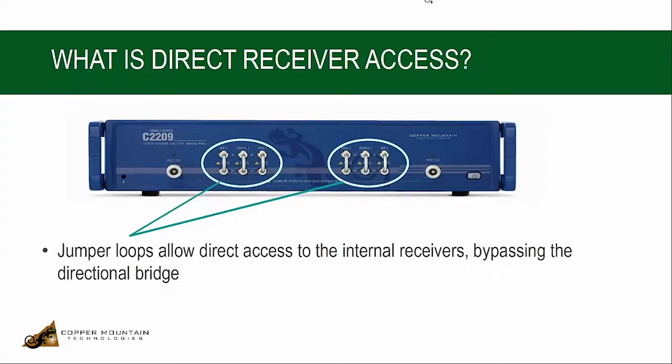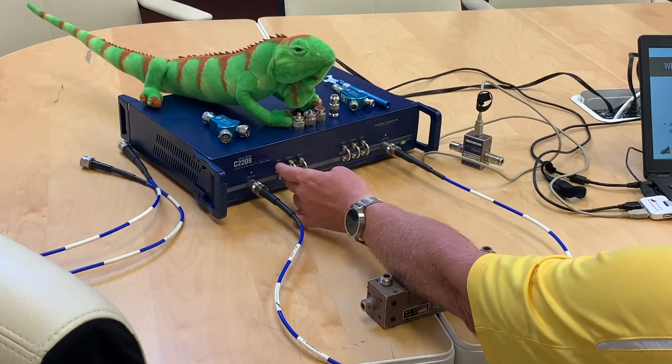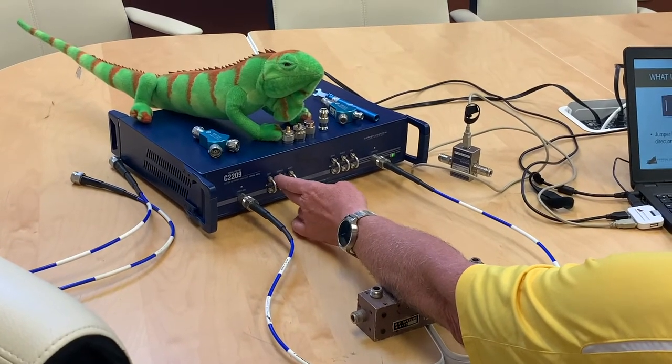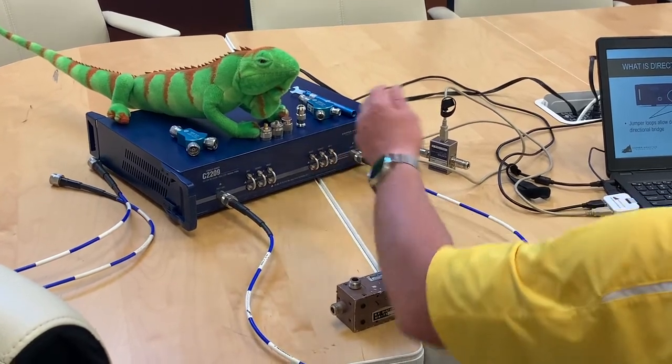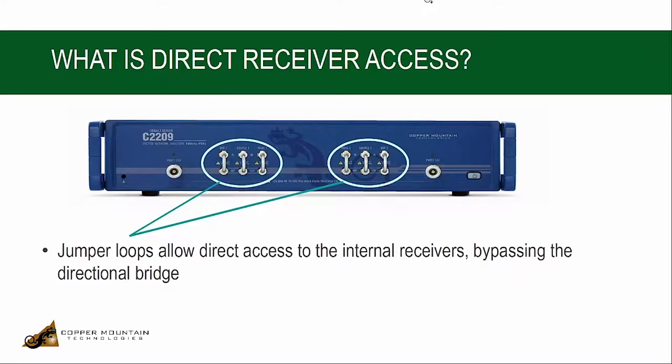If you look at the VNA, you can see on the front that there are six jumpers. There's the jumper for the incident signal, a jumper for the stimulus, a jumper for the reflective signal, and matching jumpers on the other side. So where do they connect?